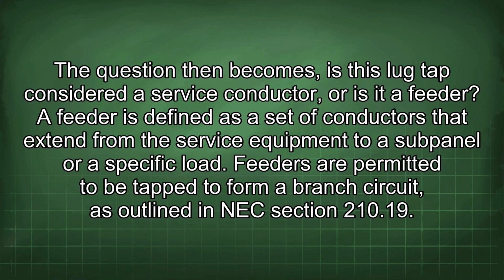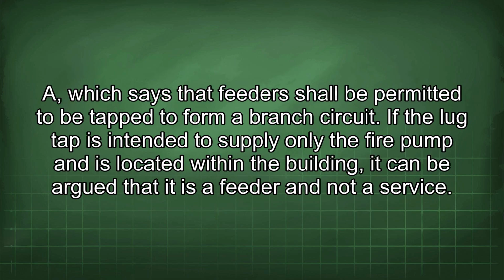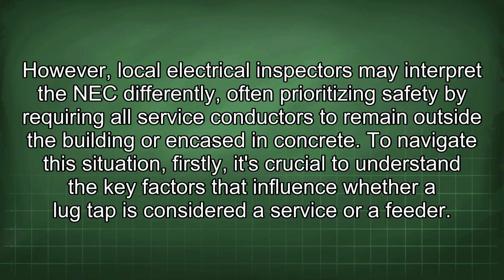A feeder is defined as a set of conductors that extend from the service equipment to a subpanel or a specific load. Feeders are permitted to be tapped to form a branch circuit, as outlined in NEC section 210.19(A), which says that feeders shall be permitted to be tapped to form a branch circuit. If the lug tap is intended to supply only the fire pump and is located within the building, it can be argued that it is a feeder and not a service. However, local electrical inspectors may interpret the NEC differently, often prioritizing safety by requiring all service conductors to remain outside the building or encased in concrete.